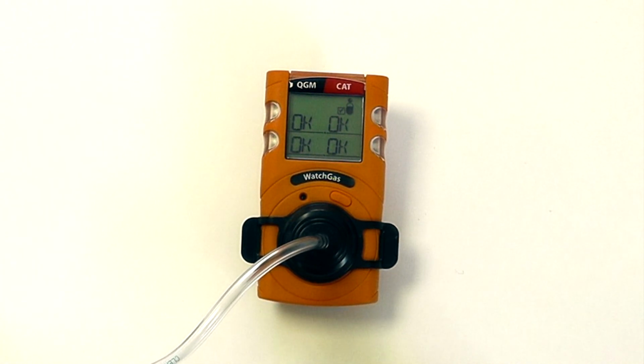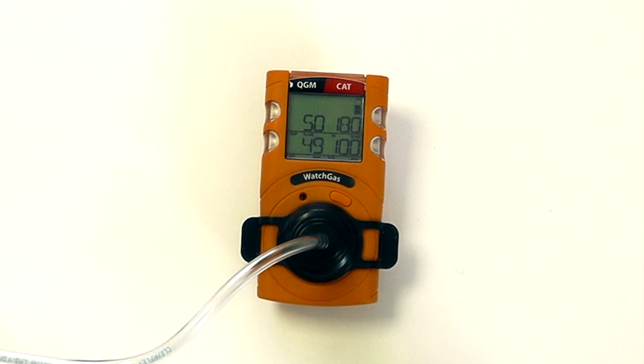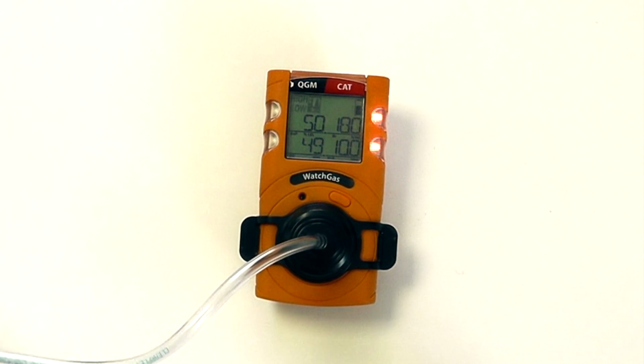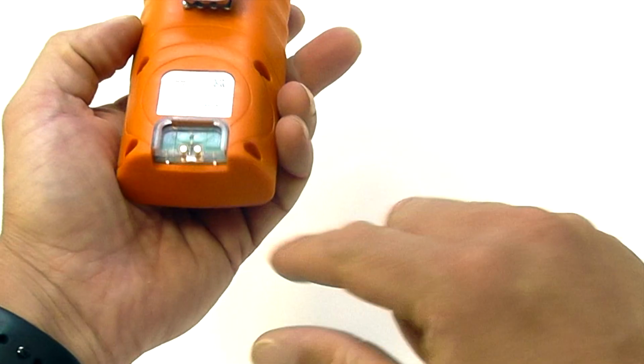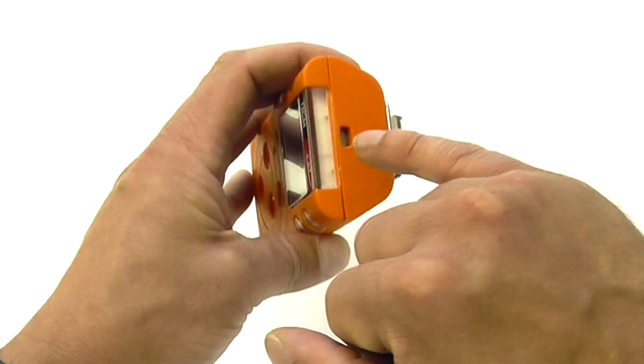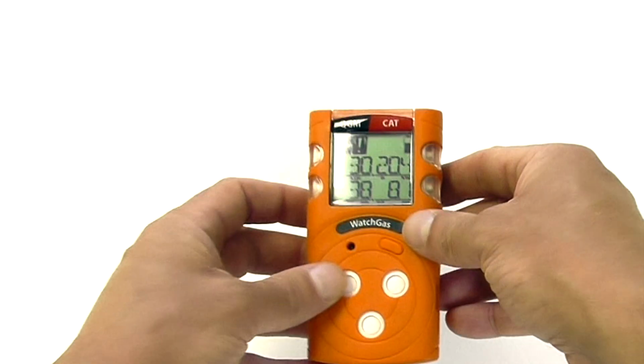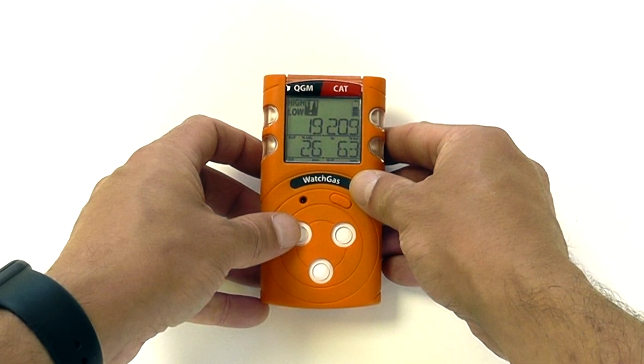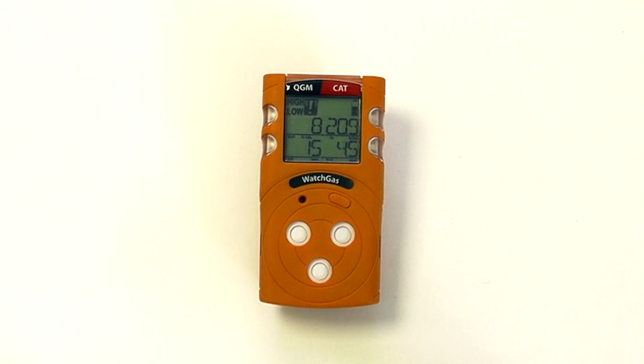As we can see, the calibration has completed successfully and all sensors are okay. Now we can remove the span calibration and we are back in normal operation. To remove the clip, we clip around the bottom, and we can see all charging is done by the lower port here and infrared communications by the top port. It will take a few seconds for the instrument to stabilise and come back down to ambient conditions.